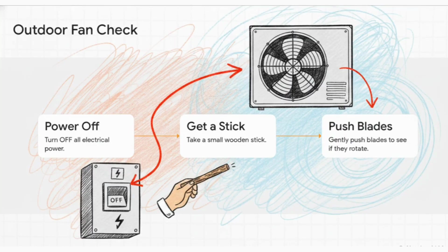But what if the compressor runs, gets dangerously hot, and then shuts down? It might be the outdoor fan motor. Here's an absolutely crucial DIY safety step to check this, especially if your AC hasn't been used in a year or two. Step 1, turn off all electrical power. I'm serious, flip the breaker completely off. Step 2, take a small wooden stick. Step 3, gently push the outdoor fan blades through the safety grill just to see if they rotate smoothly. Often, they get jammed up from rust and disuse, and if that fan is stuck, the compressor can't release heat, so it overheats and trips the whole system.